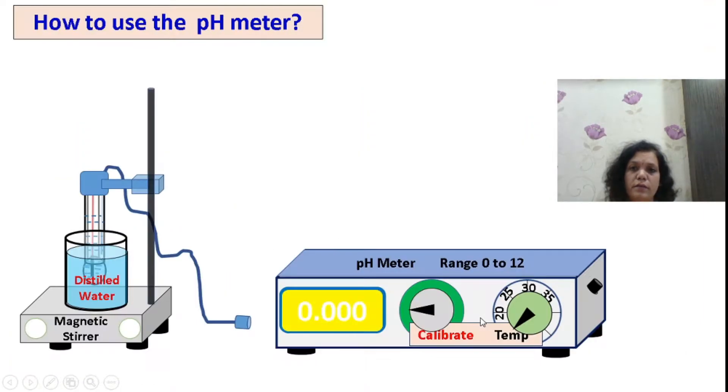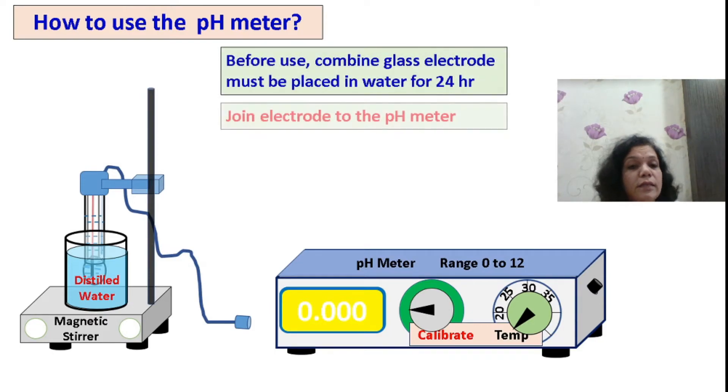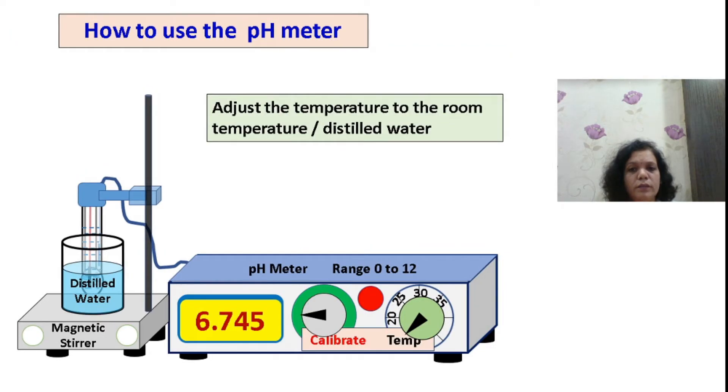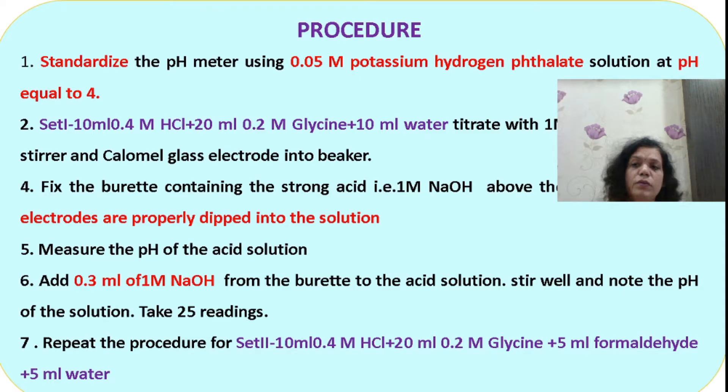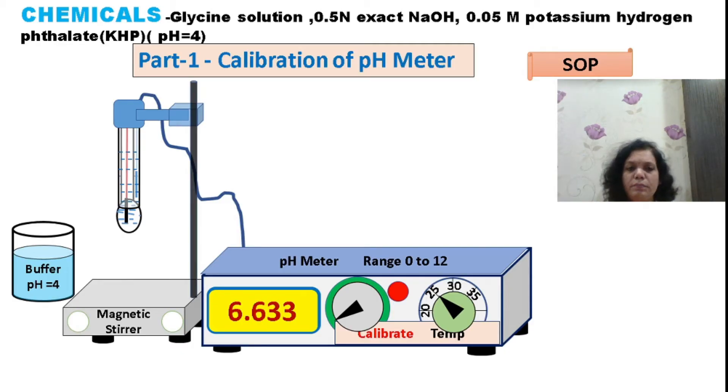How to use the pH meter: Always keep the glass electrode in contact with water to remain active. Make sure your glass electrode is dipped in water 24 hours before use so the glass becomes active for ionic exchange reactions at the glass surface. Join the pH meter, power it on, and check the temperature knob to ensure it represents room temperature. You have to use buffer solutions - either ready-made buffers at pH 7, 4, and 9, or 0.05M potassium hydrogen phthalate solution.